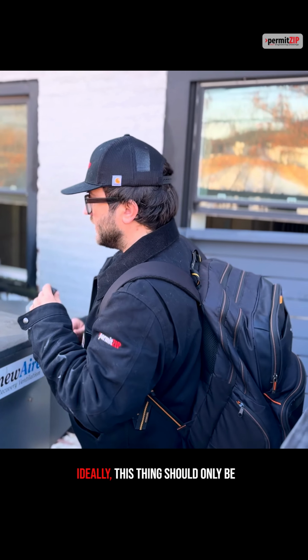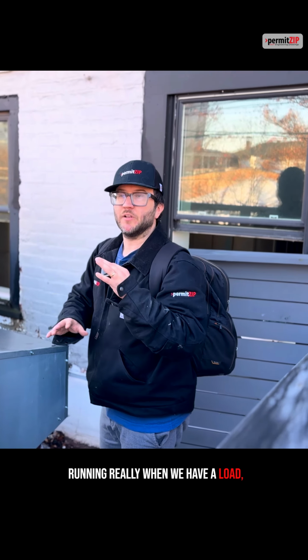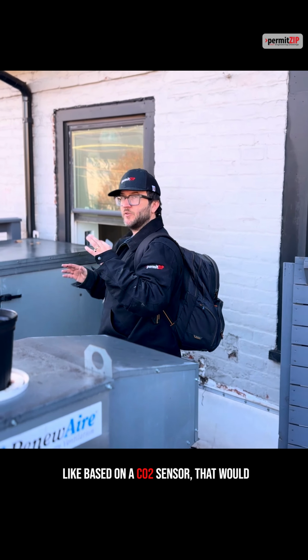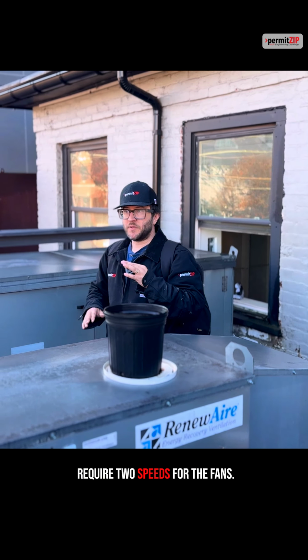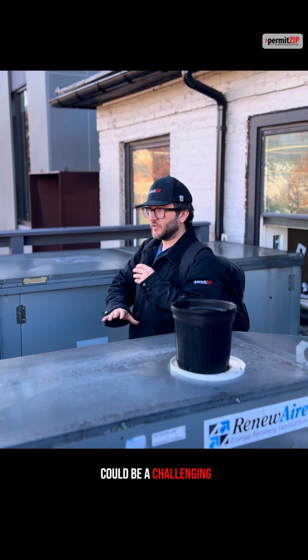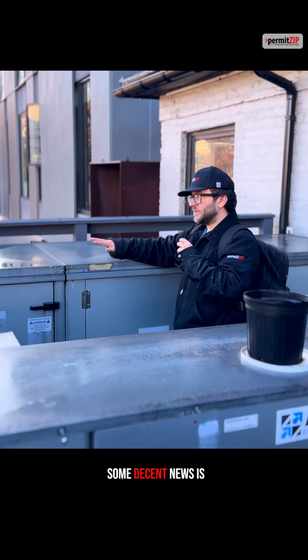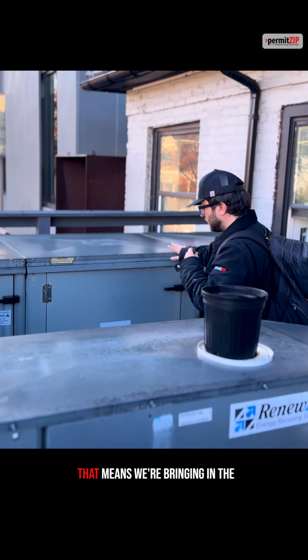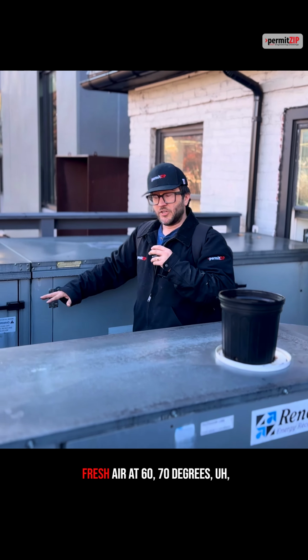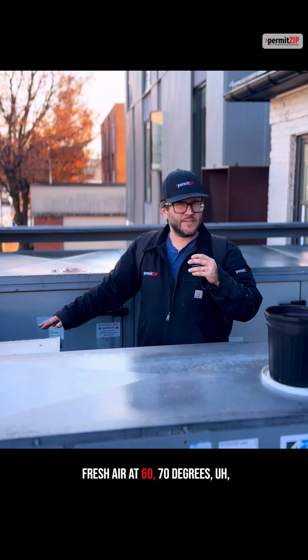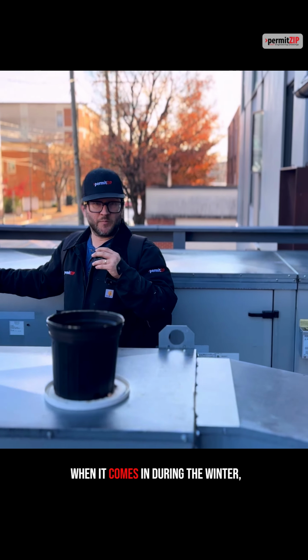That's a mystery. Ideally this thing should only be running really when we have a load, like based on a CO2 sensor. It would require 2 speeds for the fan, so that could be a challenging thing to unpack. Over here, some decent news is that it's a gas-fired unit.